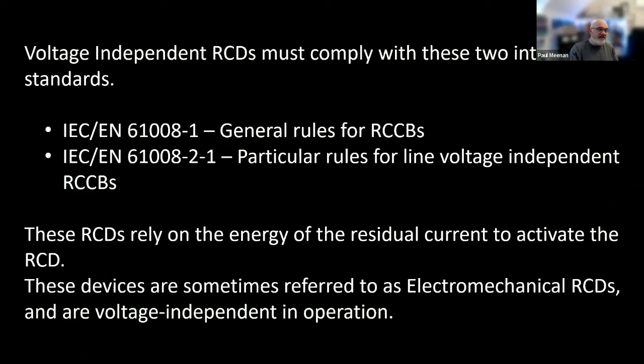Now, there are two types of RCDs I just wanted to skip through. Voltage independent RCDs must comply with the International Standard 61008, parts 1, 2, and 1. These RCDs rely on the energy of the residual current to activate the RCD. So the leakage current, that residual current, is what activates it. They are often referred to as the old clunky electromechanical RCDs, and they are voltage independent in operation.